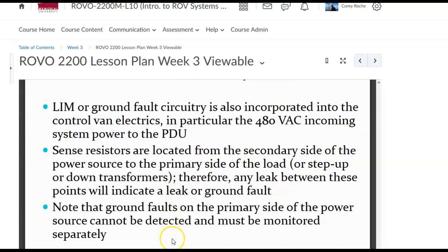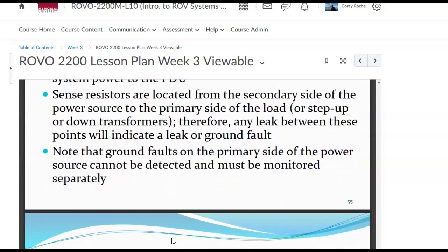LIM, or ground fault circuitry, is also incorporated in the control van electrics, particularly the 480 VAC incoming system power to the PDU. Sense resistors are located from the secondary side of the power source to the primary side of the load, or step up/down transformers. Any leak between these points will indicate a leak or ground fault. Note that ground faults on the primary side of the power source cannot be detected and must be monitored separately.